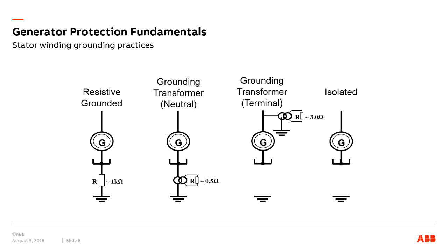And on the grounding side, there are different ways of grounding the generator. These are some of the common ones. The one on the left is resistive grounding, which is typically a low impedance grounding, where a resistor is connected between the generator neutral and the ground. This resistor limits the ground fault current. Which means the lower the resistance value, the more the damage to the generator winding during an internal fault. So if it's a low impedance grounding, the fault current can typically be in the range of 200 to 400 amperes. And then the other method is high impedance grounding. High impedance grounding uses a single phase distribution transformer connected between the generator neutral and the ground.